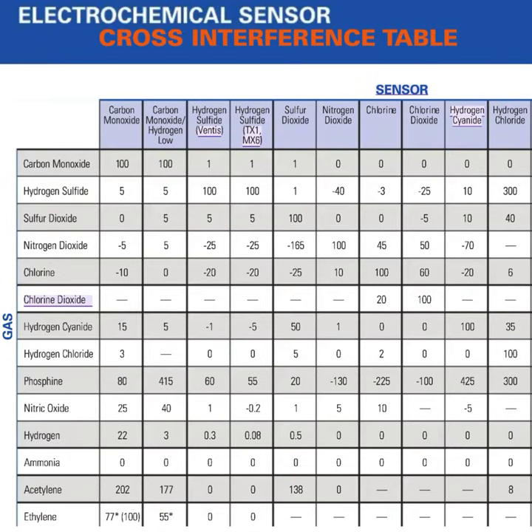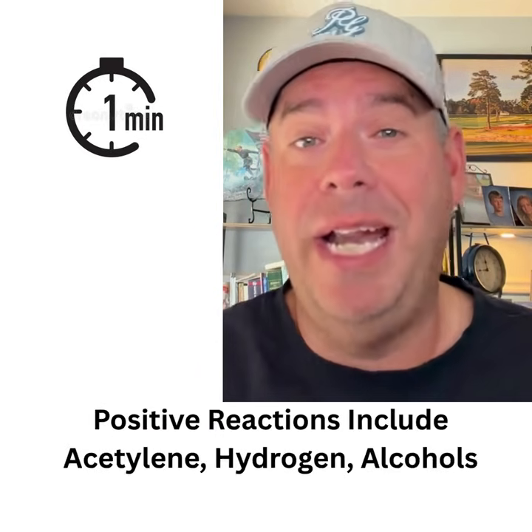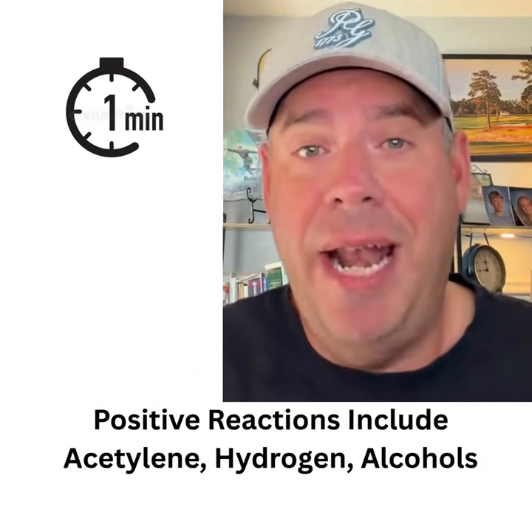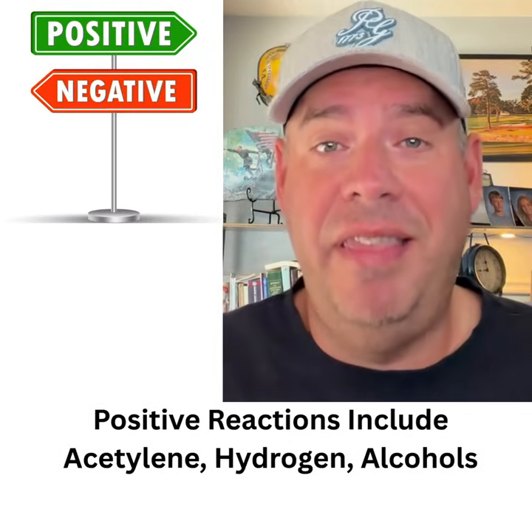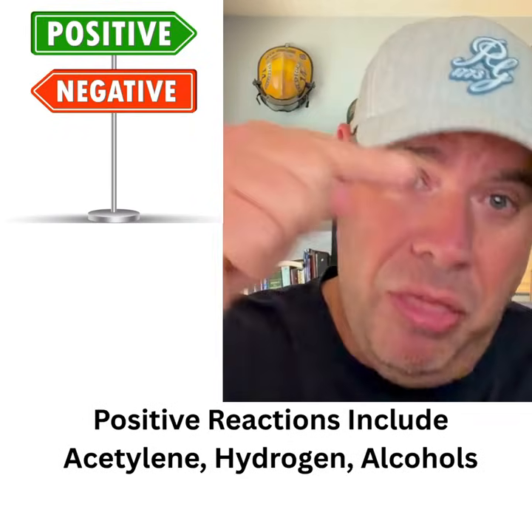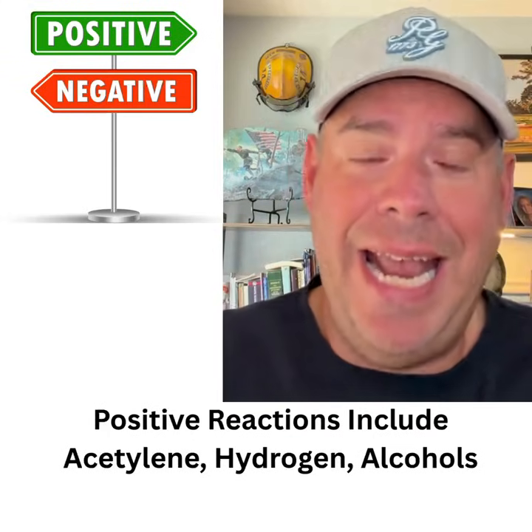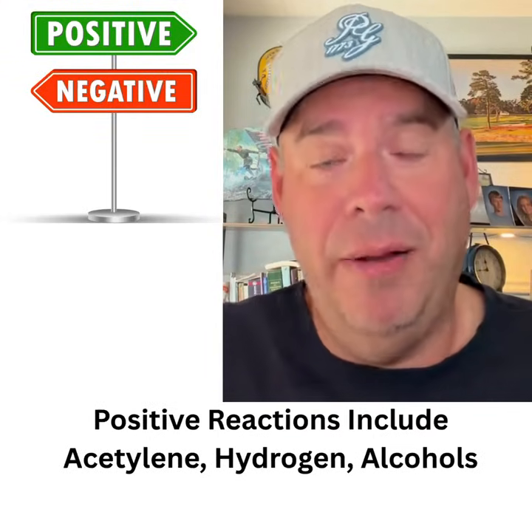Why 500 parts per million? Because most of our CO sensors don't go higher than that. So you'll see 499 and it'll kind of block out. That is a cross sensitivity because that gas is able to make it through the filter and react in that chemical, causing a reaction.